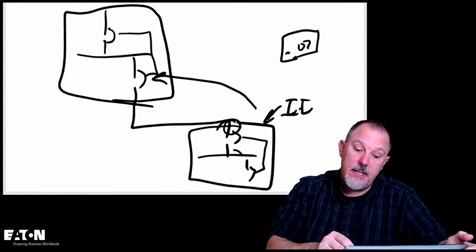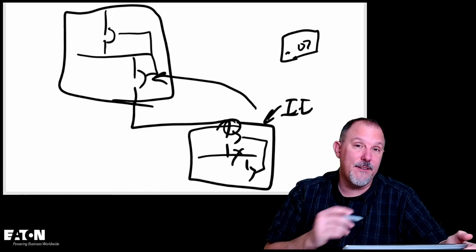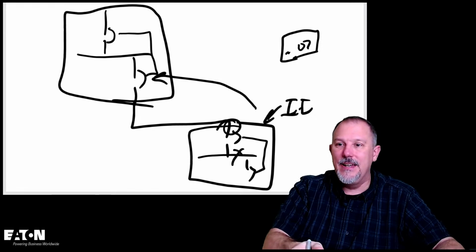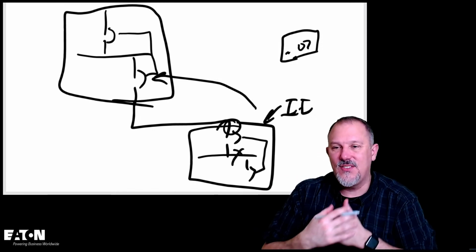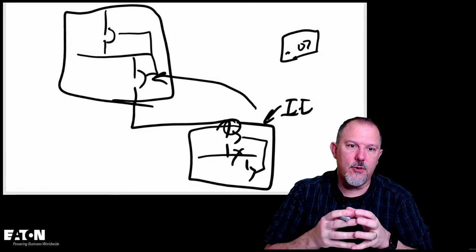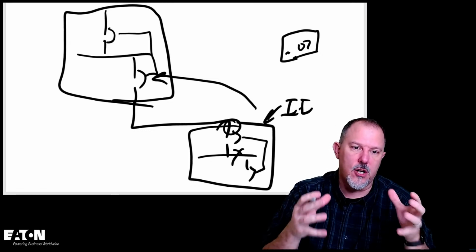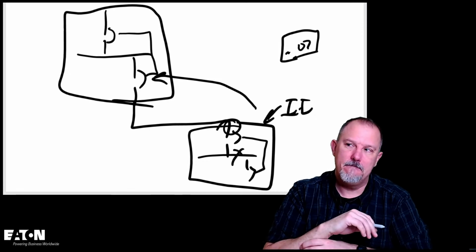But if I have a fault here, then it's going to clear very fast, but I don't have a standard that says because you've cleared so fast that you're not going to have that plasma cloud that's going to cause a line side propagation. Make sense?